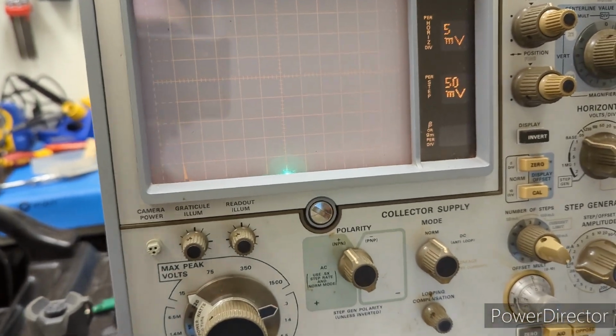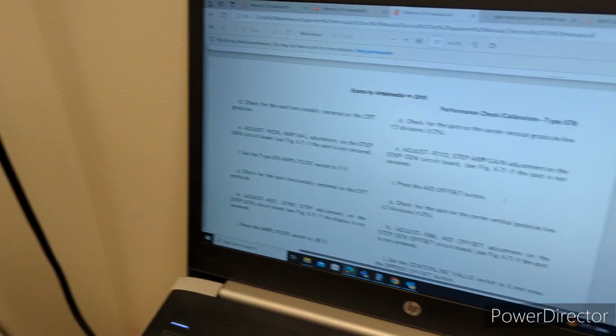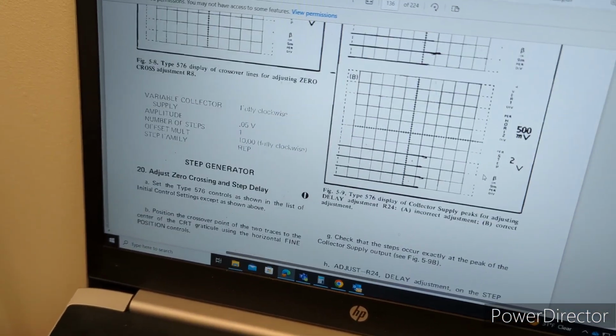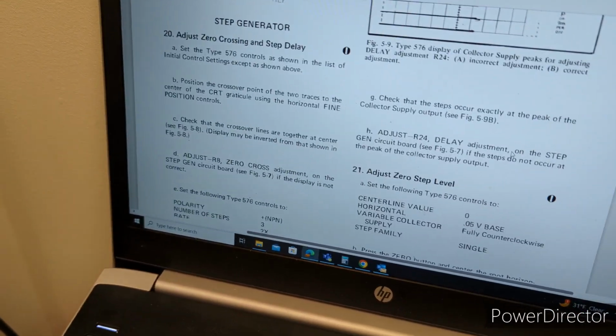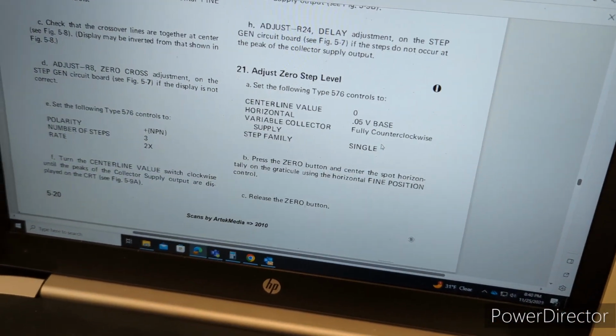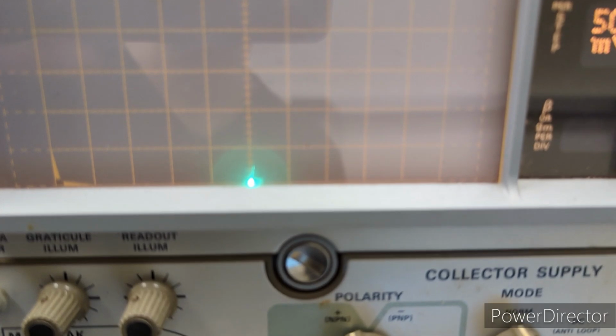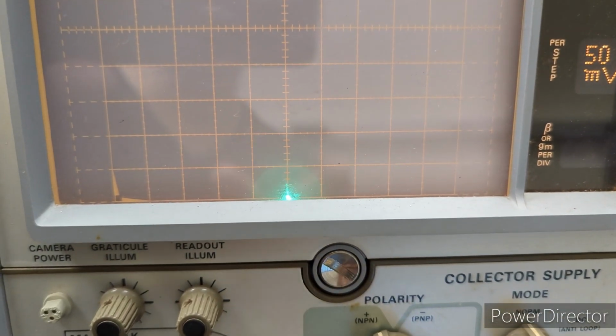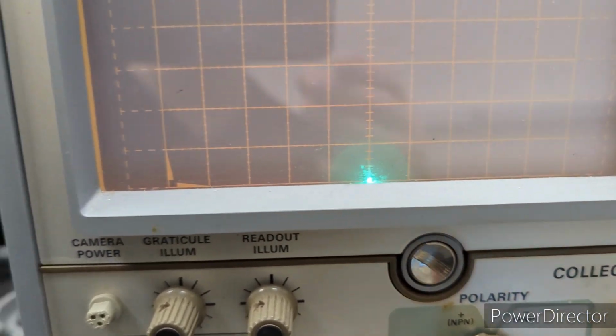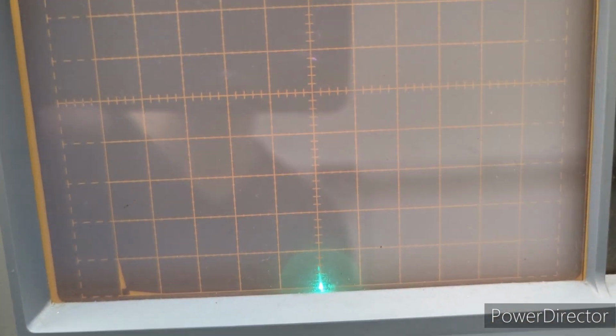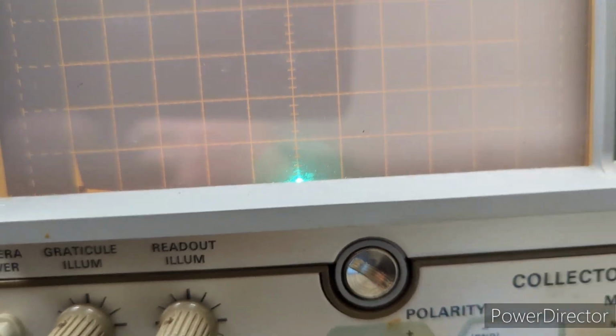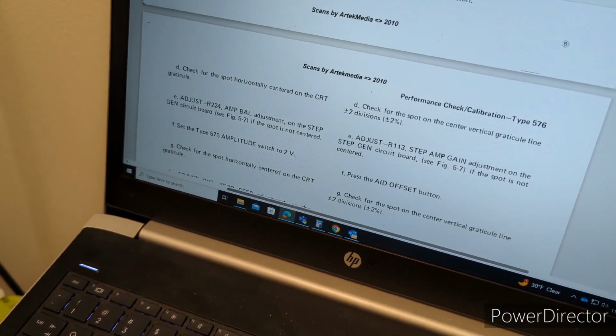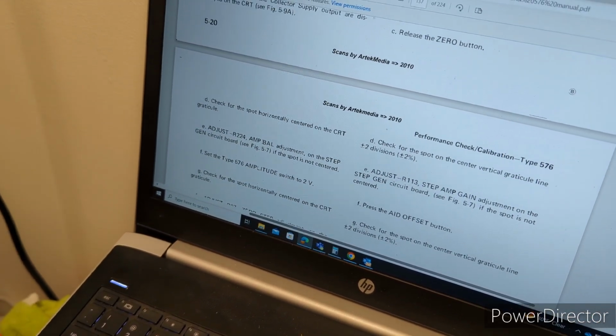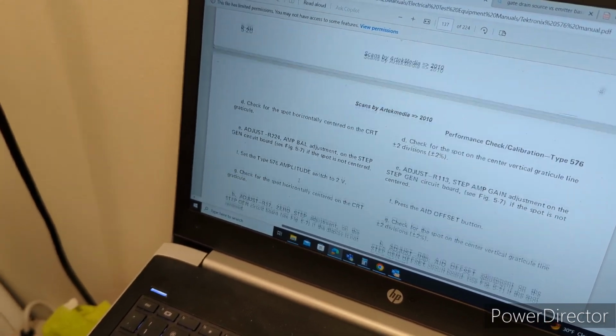Okay, so now we've moved on to the step generator adjustments, and I looked through step 20, adjust the zero crossing and step delay. Everything looked good there. And now on to step 21, adjusting the zero step level. This was another step that gave us issues the last time we tried it. The trace would just completely disappear from the screen, or it wasn't there at all. And now it's centered on the center graticule as it should be. It will require no adjustment. If it's not, you should make an adjustment at R224, the amp balance adjustment. So yeah, we're looking good there.